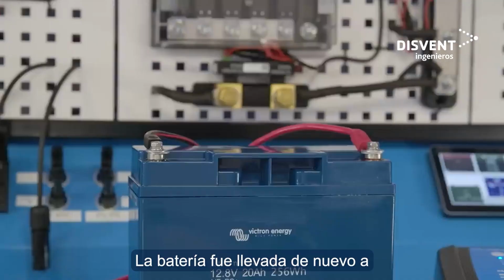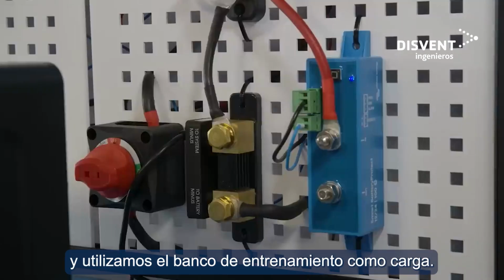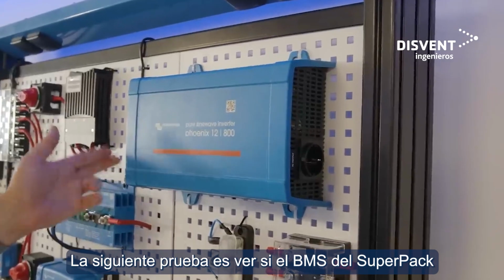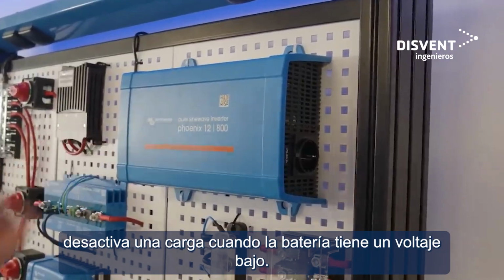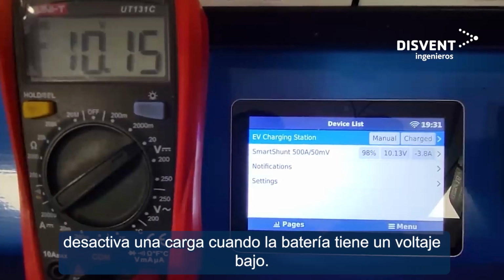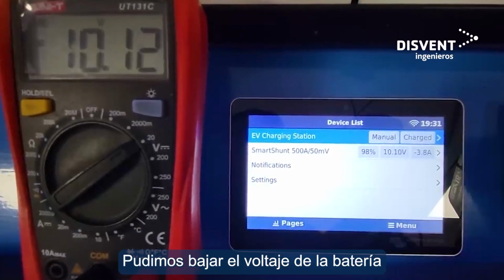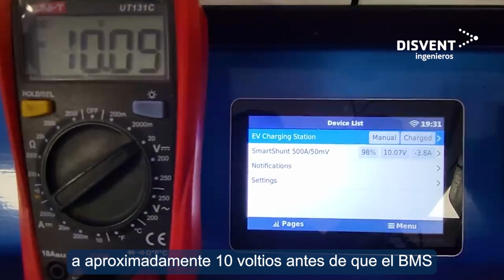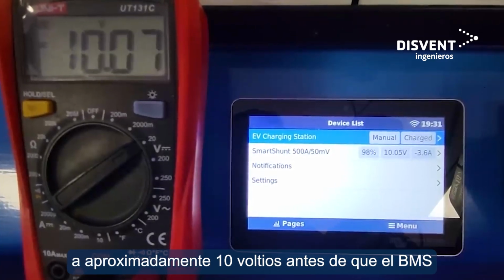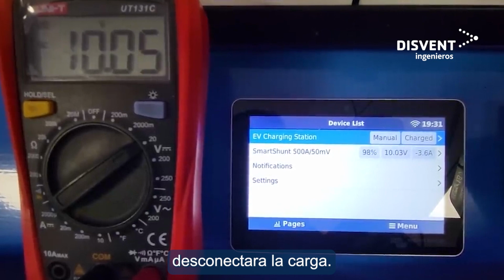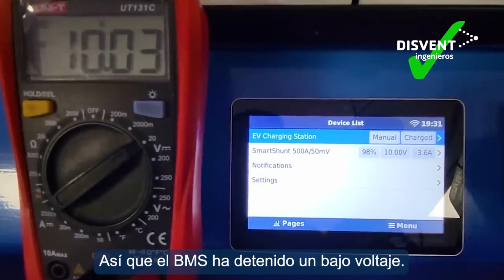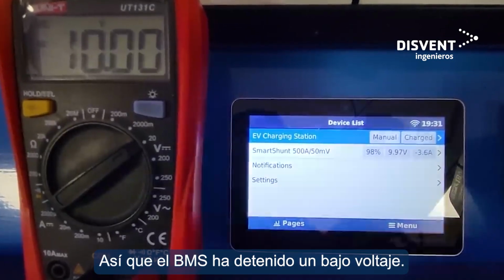The battery was brought back to normal room temperature again, and we used the training bench as a load. The next test is to see if the SuperPack BMS disables a load when the battery has a low voltage. We were able to take the battery voltage down to approximately 10 volts before the BMS disconnected the load. So the BMS has stopped an undervoltage.